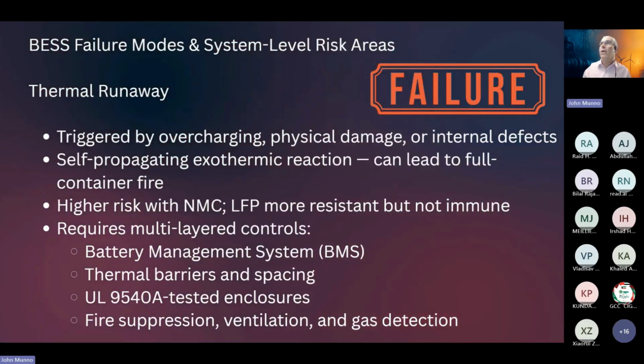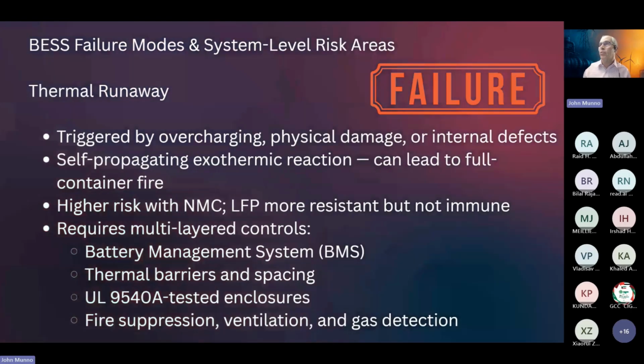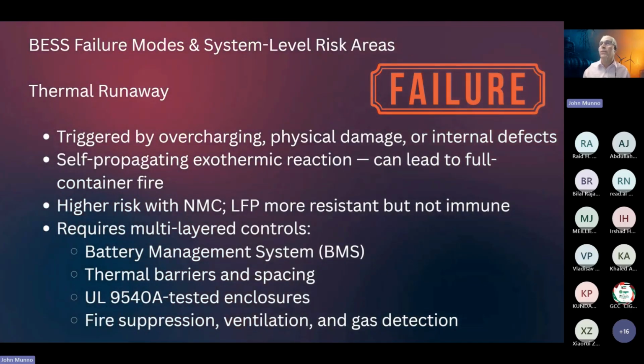So what can go wrong? Thermal runaway. We hear thermal runaway, and it can be triggered by overcharging, physical damage, or internal defects. It's self-propagating, it's exothermic, it gives off heat when it starts, and it can lead to a full container fire. And it's a higher risk with nickel, but lithium iron phosphate is still possible. It's not immune to them. I know in the beginning we used to say, oh, lithium iron phosphate can't catch on fire, but it can, and it can off gas. And in fact, some of the concerns with lithium iron phosphate are that it can generate a larger plume or vapor cloud that has to be managed or addressed.